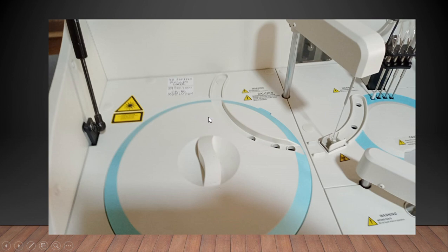This is one area I want to highlight. As you can see, this instrument has only a single probe. This is the probe which collects the sample as well as the reagent. So obviously when the instrument is running, you cannot give more samples, because the same probe will be coming to pick up the reagent and samples at different times. When you are trying to remove this cap, if the probe moves to this area, the probe may get damaged immediately.